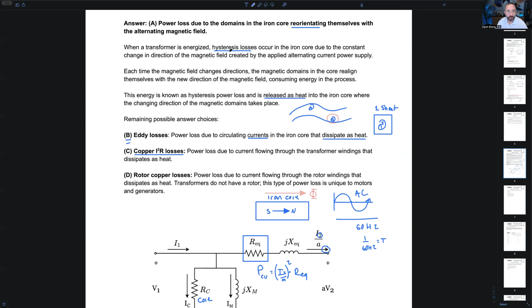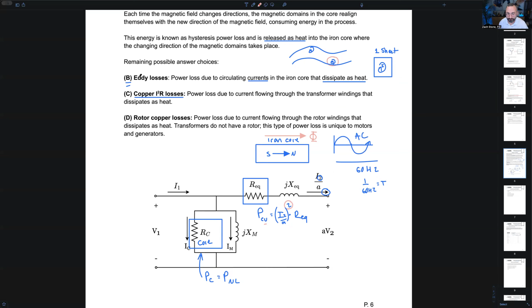You may have heard this as P no load, or no load power losses - same thing. They do not vary with the square of the current, unlike our copper losses. Your core power is the sum of your eddy and your hysteresis losses. Any questions before we move forward?